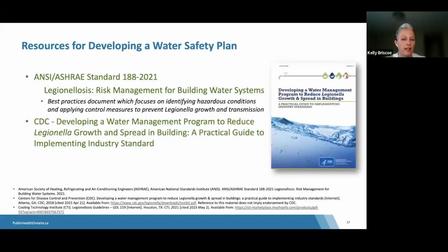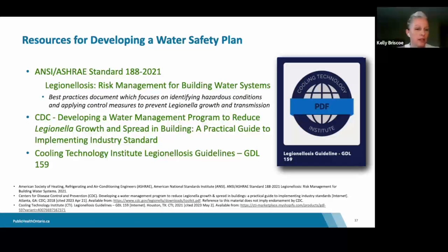We also have the CDC document that we have mentioned previously. This is a free and practical guide and models the ASHRAE document, but in more plain language. It also includes special considerations for healthcare facilities. And there was also the Cooling Technology Institute Guideline 159, which is considered best practice for the control of Legionella in cooling towers. There is a fee associated with this document, so I just wanted to make note of that.